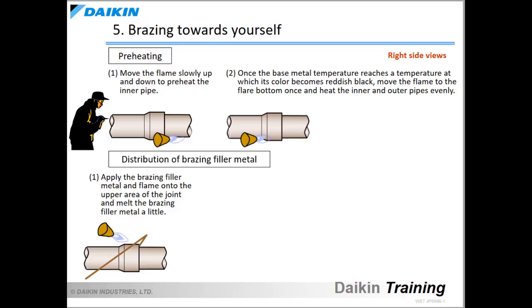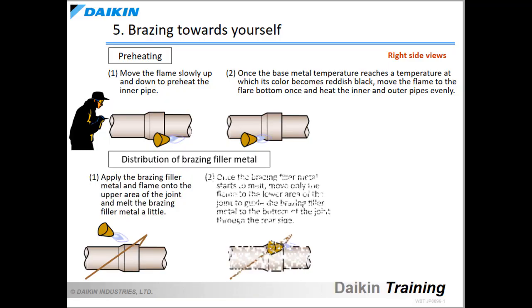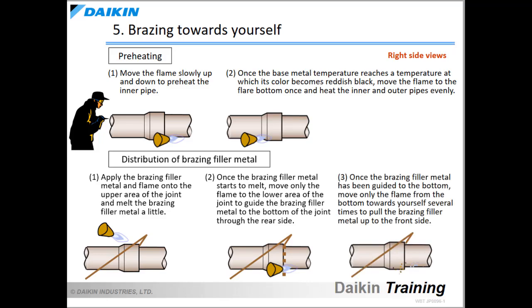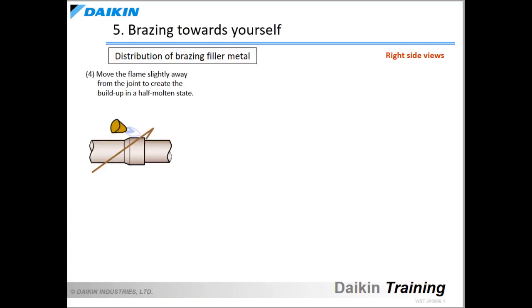First, apply the brazing filler metal on the top of the inner pipe along with the flame to melt it a little. When the brazing filler metal starts to melt, immediately move the flame downward in order to guide the brazing filler metal from the top to the bottom of the joint through the rear side. After confirming that the brazing filler metal has been guided to the bottom through the rear side, move the flame from the bottom toward yourself several times to pull the brazing filler metal up to the front side. After the brazing filler metal is pulled up to the front side, move the flame to the upper area of the joint and slightly away from it to create the build-up in a half-molten state.